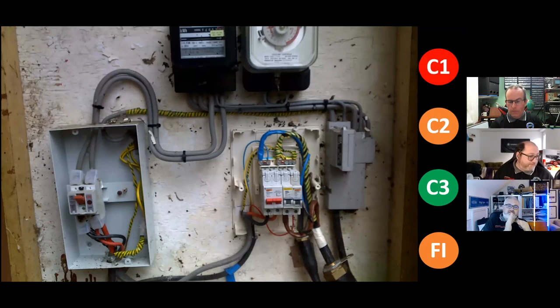The fact of the matter is, as an inspector, I would probably find that circuit and I would put a megger across it as a minimum before I left, just to see whether it is. And if I've got low insulation readings, then I'll jump that C2 to a C1. So your C2 FI might result in readings that go from C2 up to C1.